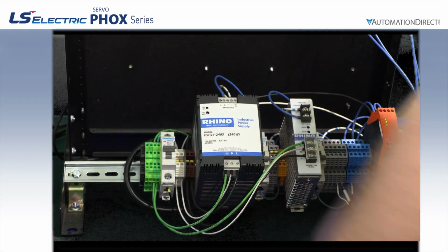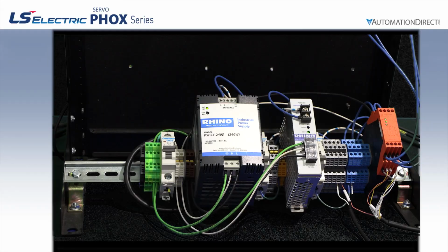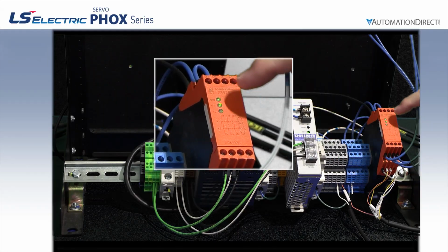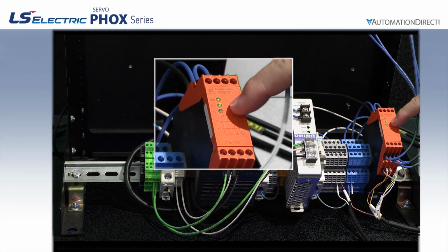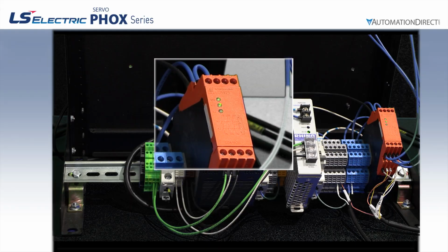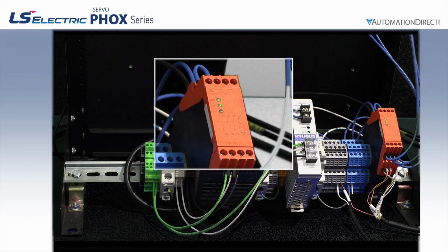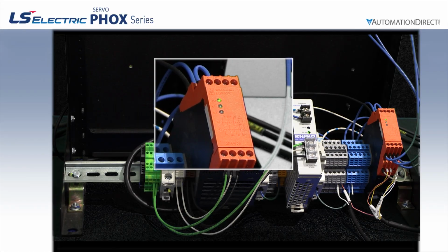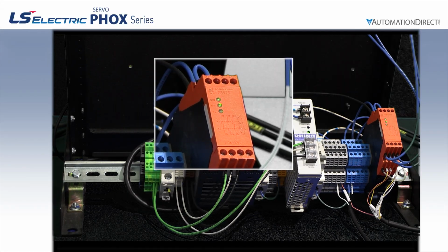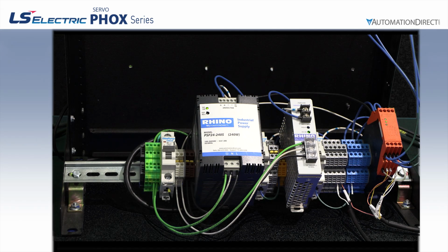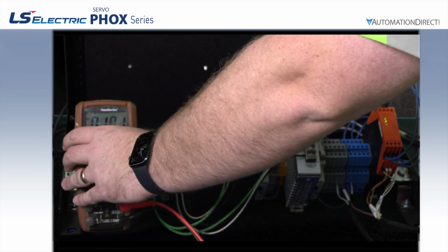And that's it. Let's try powering everything up by flipping the main circuit breaker for our incoming power. This powers up both supplies, and the safety relay turns on its power LED with its K1 and K2 LEDs indicating that everything in the emergency stop circuit is wired up correctly. Let's press our E-stop, and we see the K1 and K2 LEDs go out, indicating that it has entered a safe state. Then pull the E-stop back out, and they automatically reset and come back on. And we will run a quick meter test to ensure everything is within the correct voltage range.